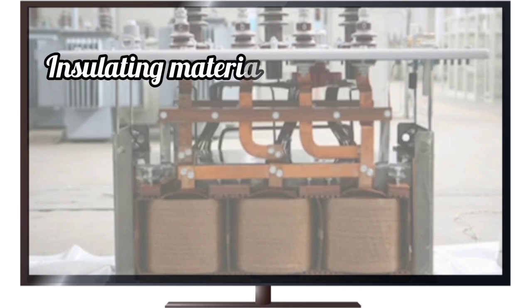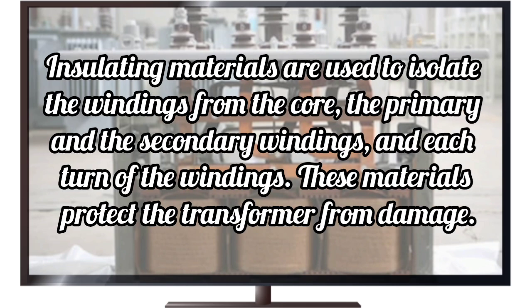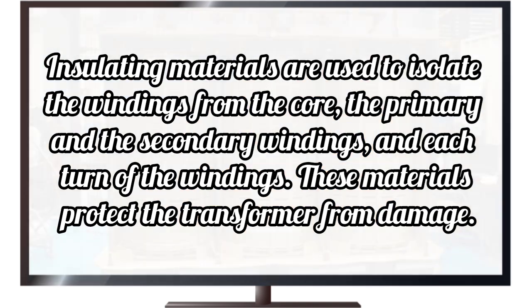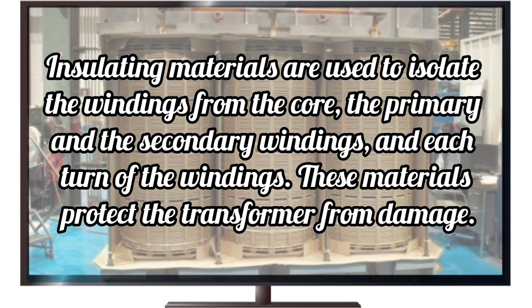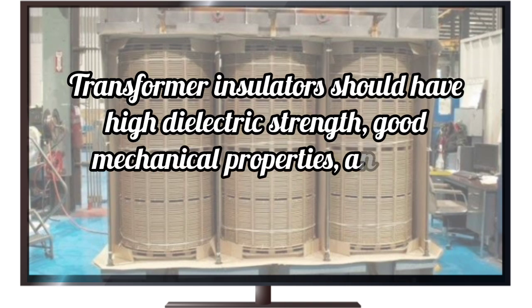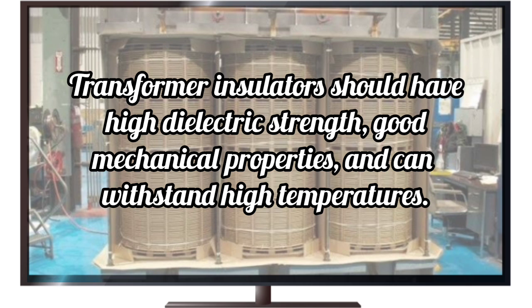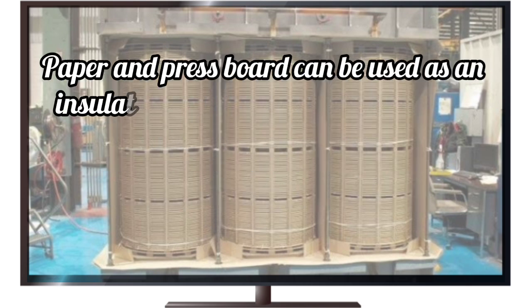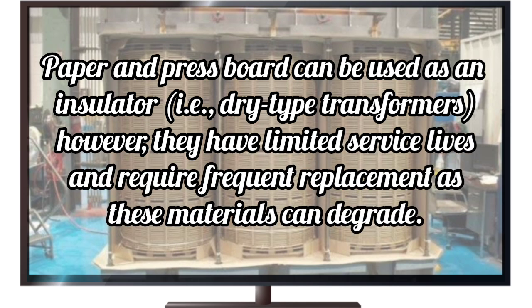Insulating materials. Insulating materials are used to isolate the windings from the core, the primary and the secondary windings, and each turn of the windings. These materials protect the transformer from damage. Transformer insulators should have high dielectric strength, good mechanical properties, and can withstand high temperatures. Paper and press board can be used as an insulator, for example, in dry-type transformers. However, they have limited service lives and require frequent replacement as these materials can degrade.